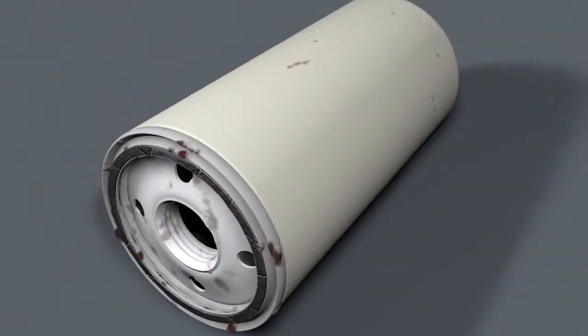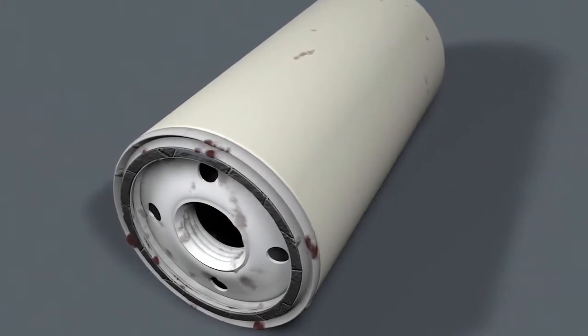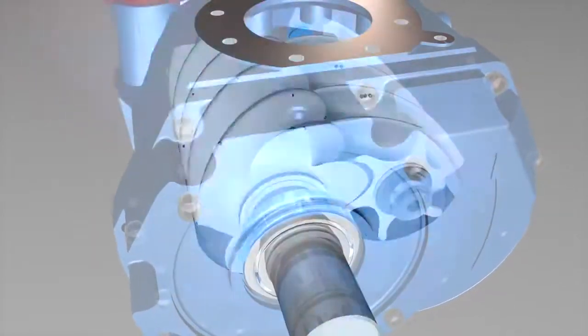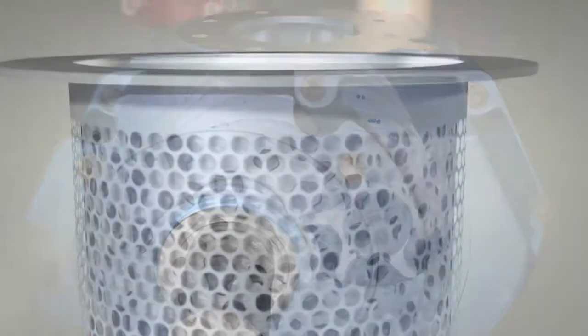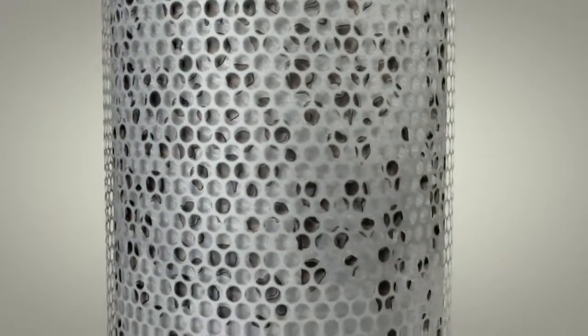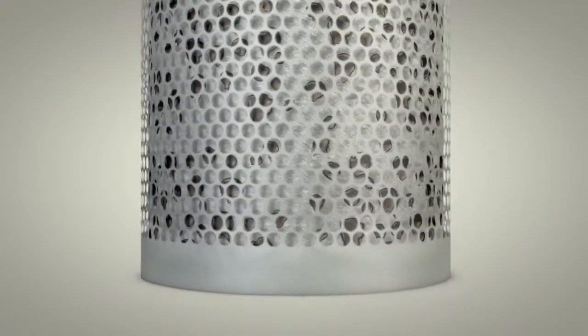Non-genuine filters are often equipped with unsuitable filter material of insufficient filter fineness, which can fail in the long term. In the worst case, the whole filter collapses and the compressor is damaged by unfiltered oil. The result of wear on the screw and bearings can even lead to a total failure of the compressor. Such an oil filter also compromises the function of the air-oil separator. So non-genuine filters often end up being more expensive than their genuine counterparts.